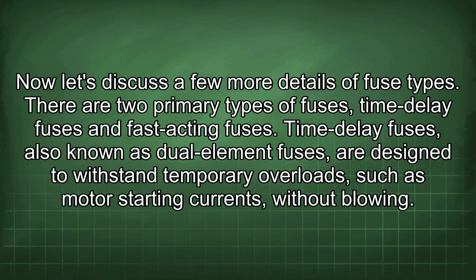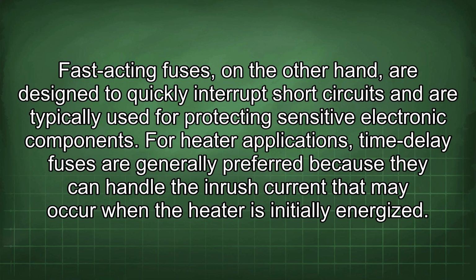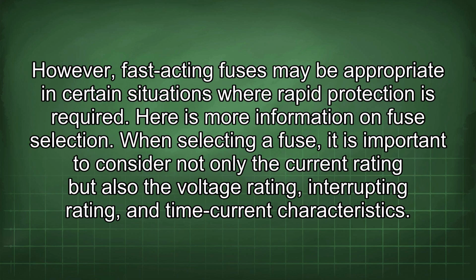There are two primary types of fuses: time delay fuses and fast acting fuses. Time delay fuses, also known as dual-element fuses, are designed to withstand temporary overloads, such as motor starting currents, without blowing. Fast-acting fuses, on the other hand, are designed to quickly interrupt short circuits and are typically used for protecting sensitive electronic components. For heater applications, time delay fuses are generally preferred because they can handle the inrush current that may occur when the heater is initially energized. However, fast-acting fuses may be appropriate in certain situations where rapid protection is required.